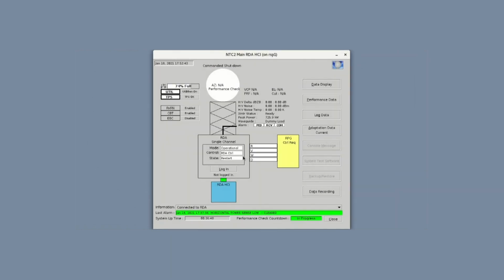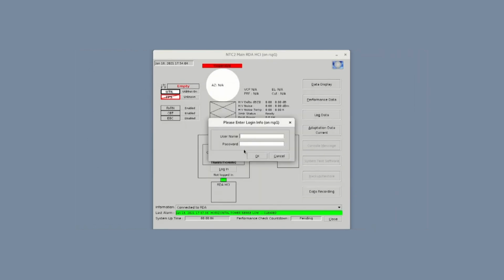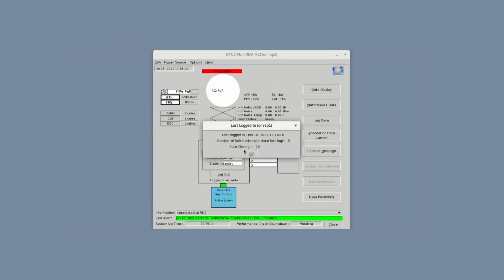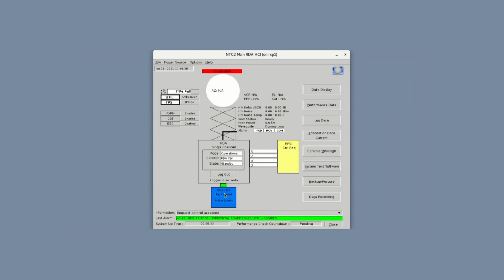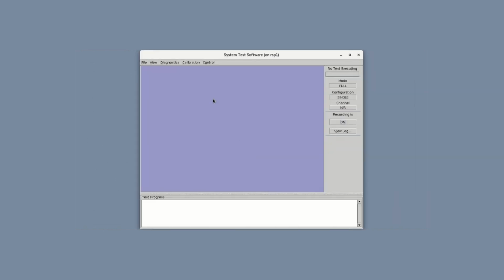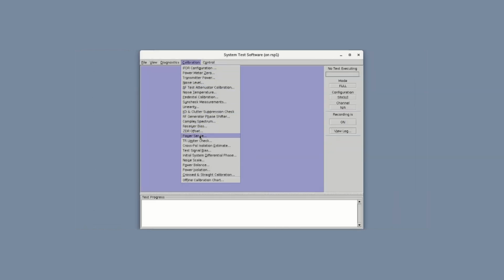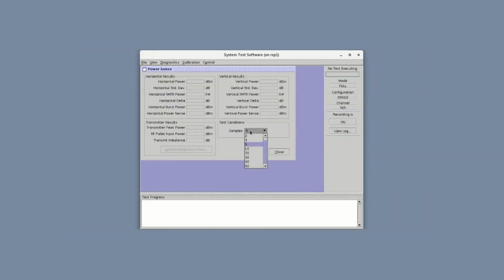Log into the main RDA HCI using username and password. In the main RDA HCI, click RDA Request Control. Click the System Test Software button and Yes to confirm. In the System Test Software window, click Calibration, PowerSense. In the PowerSense window, set samples to 10, click Run.